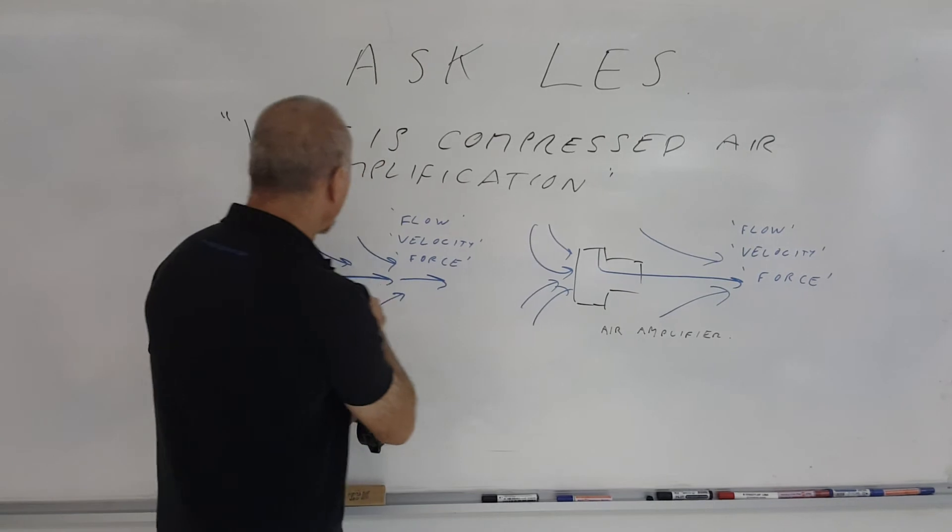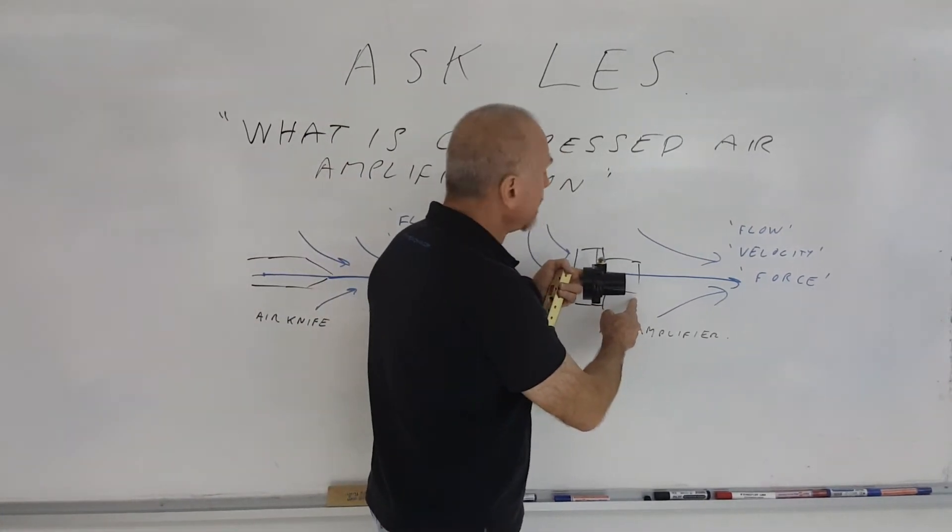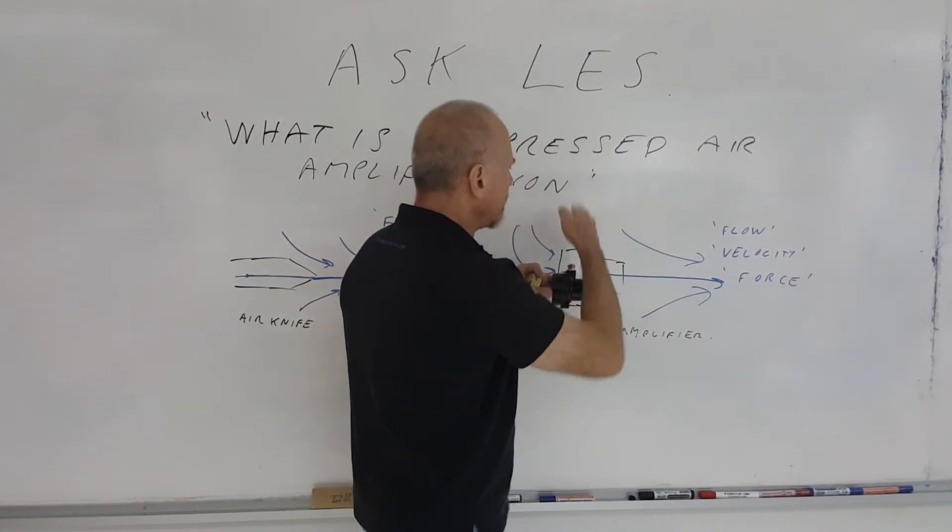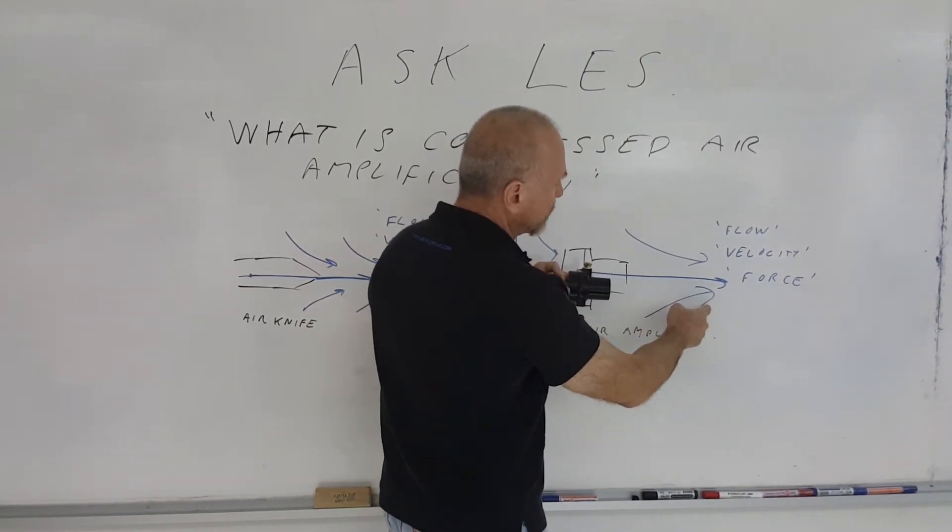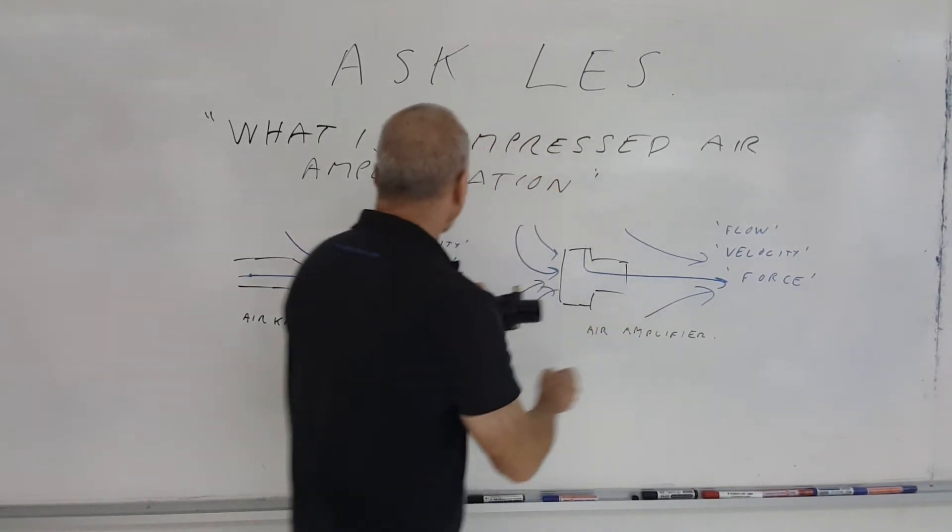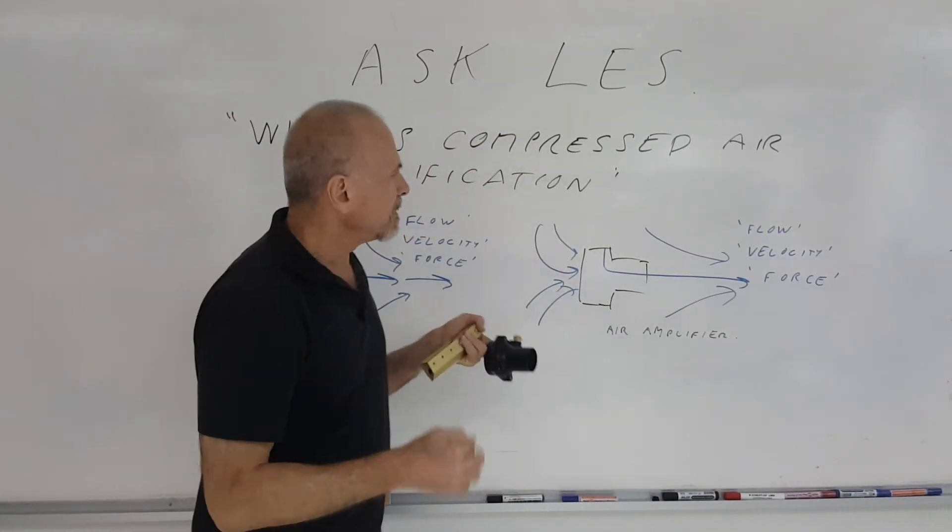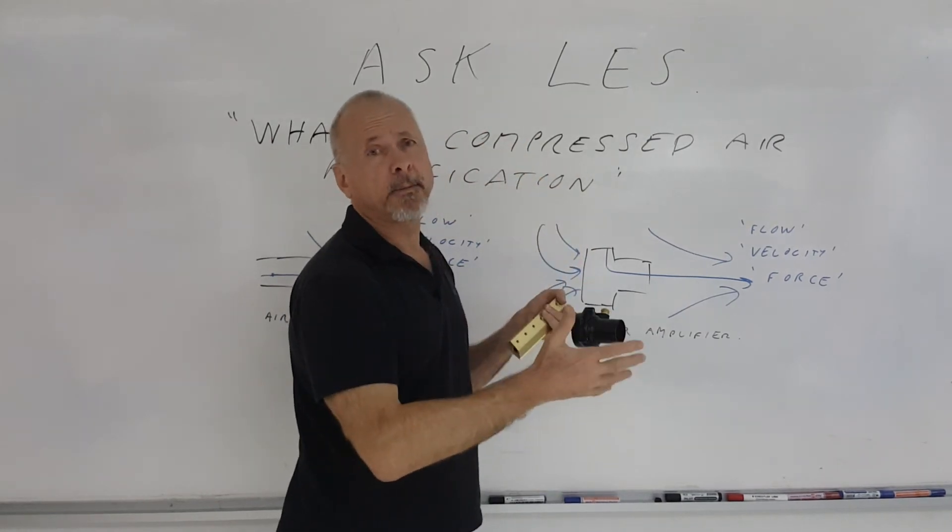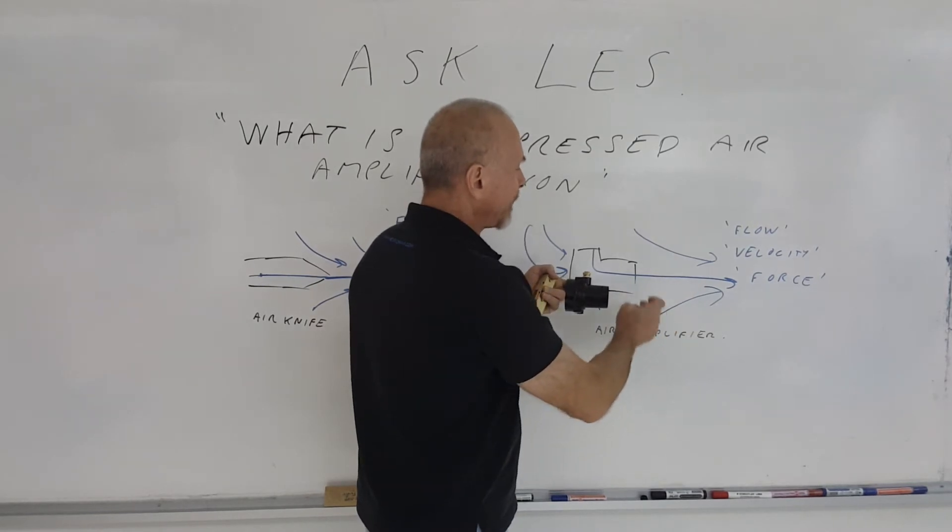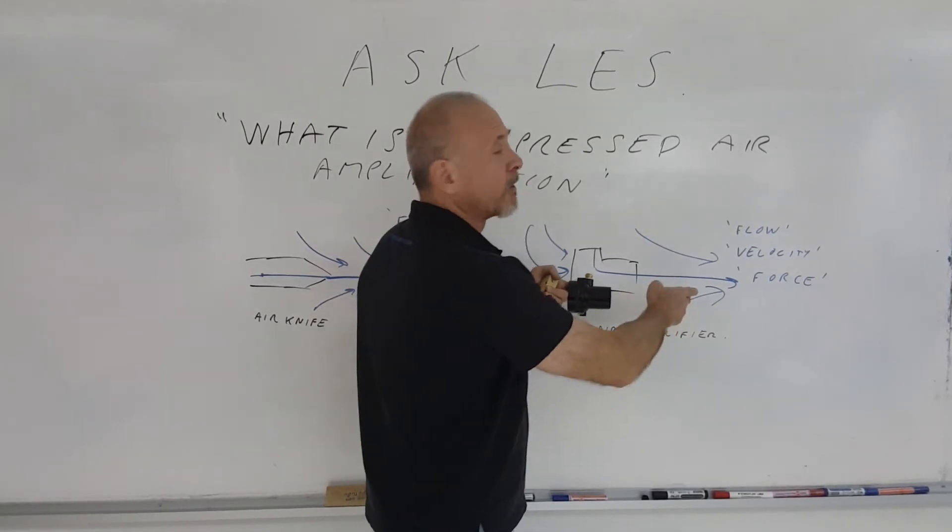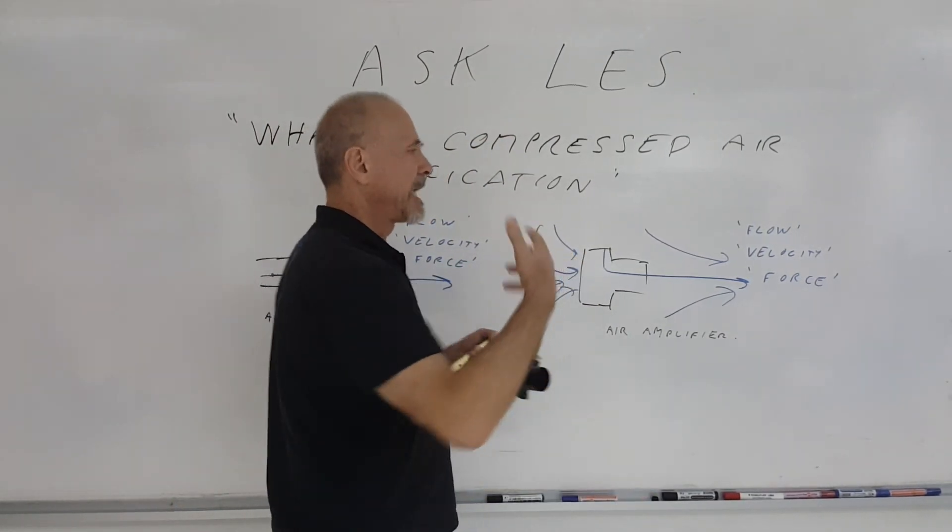So for an amplifier, for example, at the exit it may be 15, which means you're getting 15 times what the input compressed air is for flow. But when you go about 6 inches downstream from the exit of an amplifier or from an air knife, you're going to entrain more, and that entrainment on the average is another 3 times. So 6 inches downstream from the amplifier, the amplification ratio is no longer 15, it's 45.